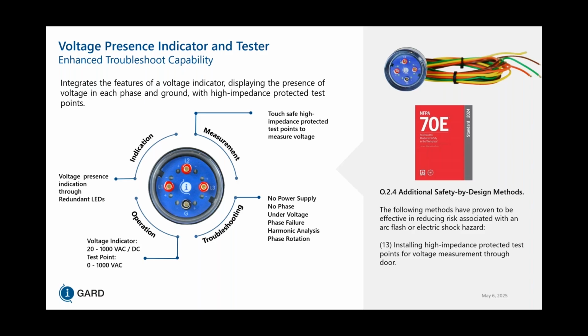The voltage indicator can go between 20 to 1000 volts AC or DC, and the test point can measure between 0 to 1000. In terms of troubleshooting, you can use this voltage test port for no power supply, no phase, under voltage, phase failure, harmonic analysis, as well as phase rotation. Further to this, in Annex O.2.4 in NFPA 70E, item 13 says installing high impedance protected test points for voltage measurement through the door reduces risk associated with an arc flash or electric shock hazard.